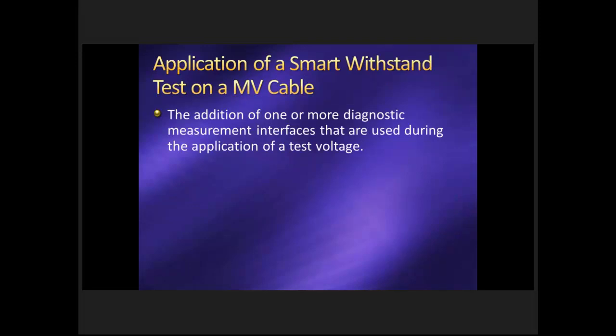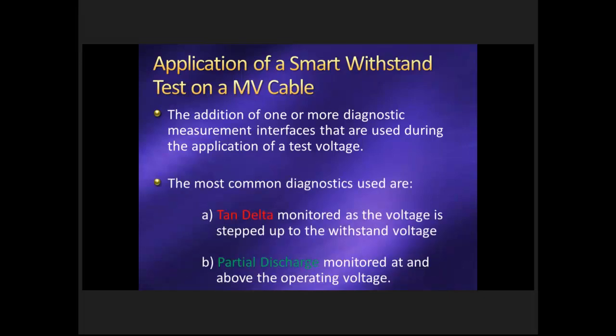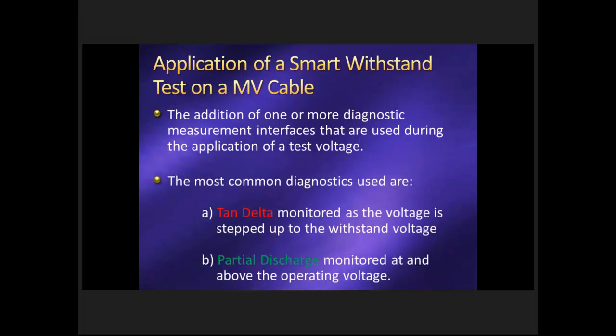Installation of the smart test on the cable. So we're going to be hooking up an additional diagnostic measurement interface while we apply the voltage. The two most common methods are without doubt tan delta or dissipation factor, and I refer you to IEEE 400.2 on that, and the other one is partial discharge. And both of those methods can be applied.